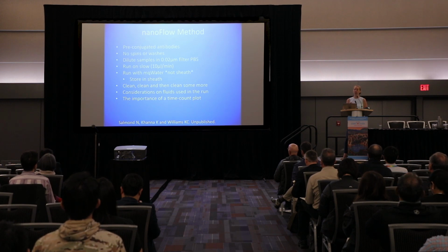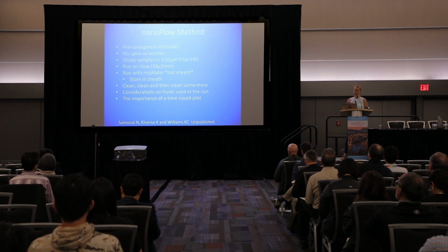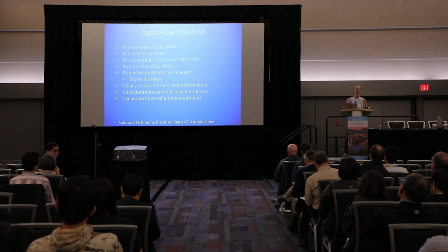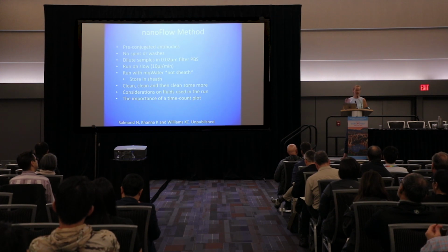We run in milliQ water. We have found that milliQ water has less noise in it than sheath. But we do store in sheath, because sheath has the properties to prevent any type of growth within your lines.